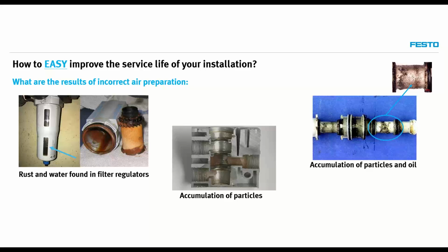Or sometimes it can even block some components, because the tolerances we include in our products, or the grease we are using, are not designed to have these particles inside. Same with oil, for example. Here we see a cutout of a valve, where you see, even at microscope level, a lot of particles, and also a very oily substance.